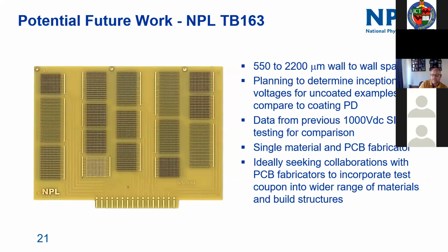The other thing we potentially would like to do is look at via breakdown. We've done this with 1,000 volt DC previously, and we've seen significant differences between the breakdown at these higher voltages and what might be expected if you extrapolate from lower voltages. At the moment, we have this simple PCB with wall-to-wall spacings ranging from about 0.5 millimeter up to just over 2 millimeters. We'll do some inception voltages on uncoated samples to see what the inception voltage is within PCBs, but it will only be a single material on a single PCB fabricator.